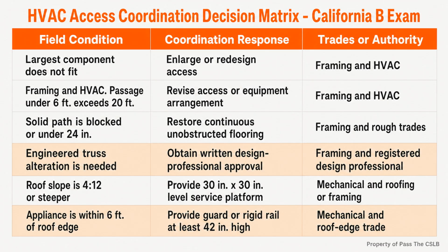A separate edge condition applies when the appliance is within 6 feet of a roof edge or a similar hazard. Guards or rigidly fixed rails at least 42 inches high are required on the exposed side under the mechanical code provision identified in the research. Do not mix those two triggers. Roof slope addresses the need for a level service platform. Proximity to the edge addresses the guard or rail condition.